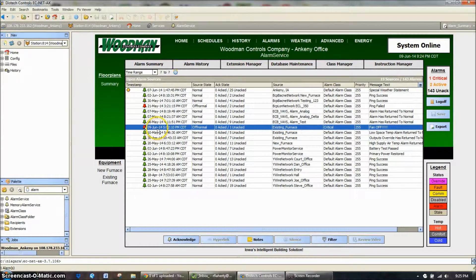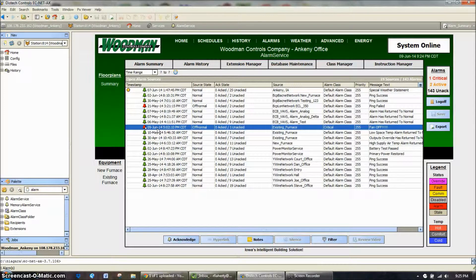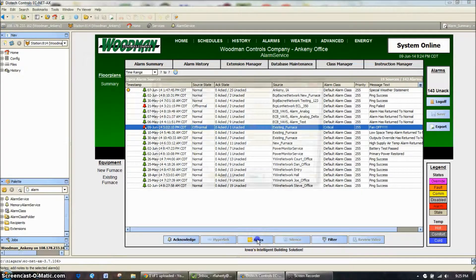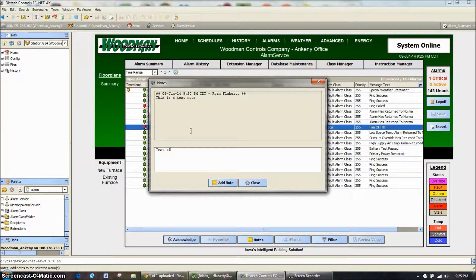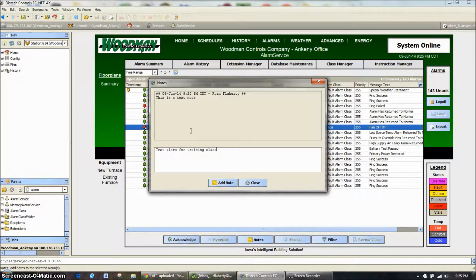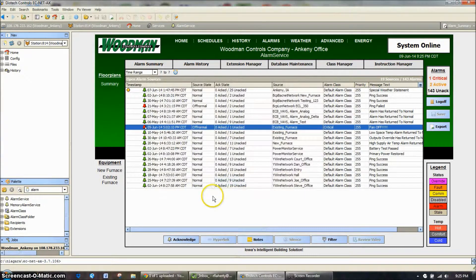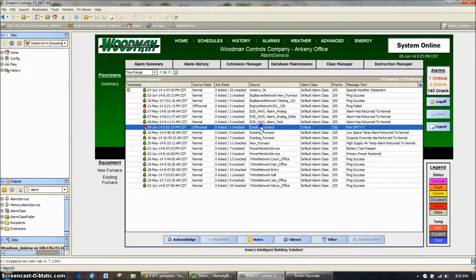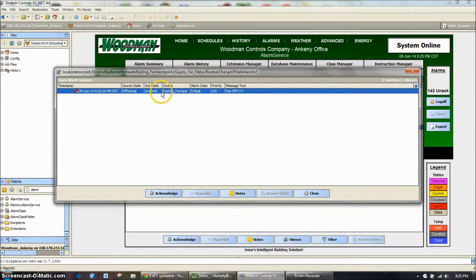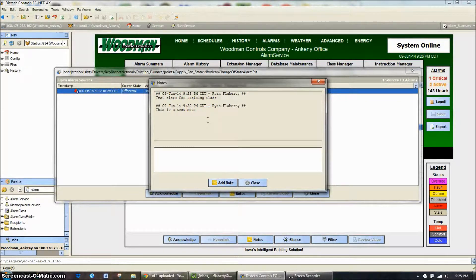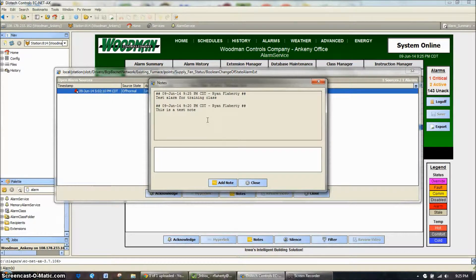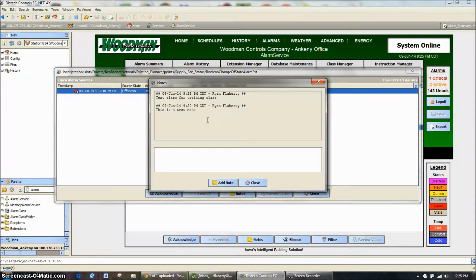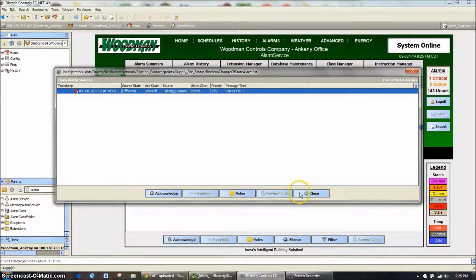Another item for in here is you can take notes on an alarm. So if there's a room temperature that you've been having trouble with, and you want to keep track of what's been happening with it, you can add notes to that alarm. So right here, I already added one note calling this a test note, and this was a test alarm, test alarm for training class. And we put that in there, and now we have a note. So whenever this alarm comes in, we should be able to click on it, and we can see whatever notes are in there. So we can just click on the notes, and they'll be running totals of what we've done to correct that. So if you have a room that has been hot and notoriously bad whenever someone leaves the coffee pot on, or the refrigerator overheats, or whatever the problem might be, you can keep track of it so the next guy that comes to look at this alarm can see the notes, see what's happened, see what kind of service steps and actions have been taken on that space.